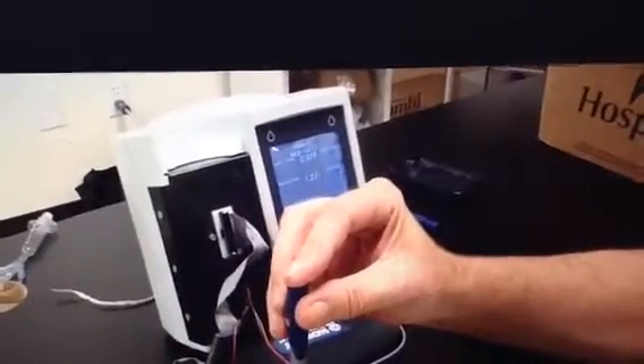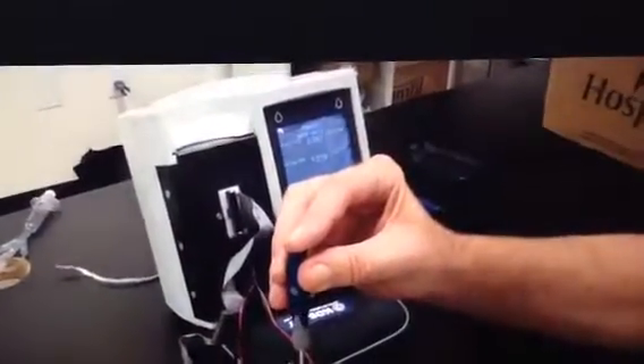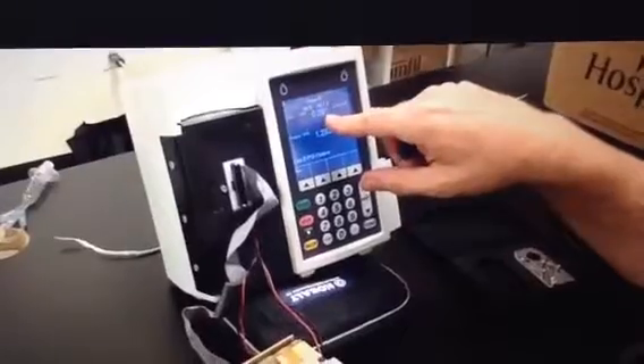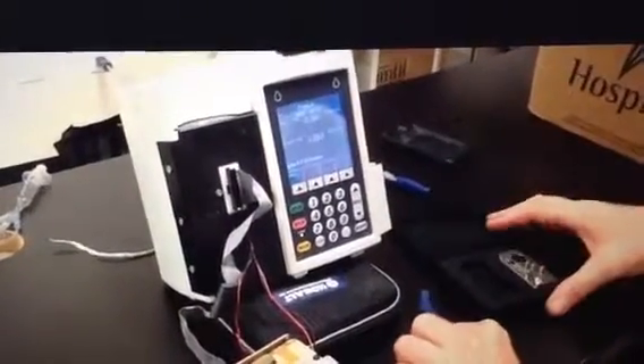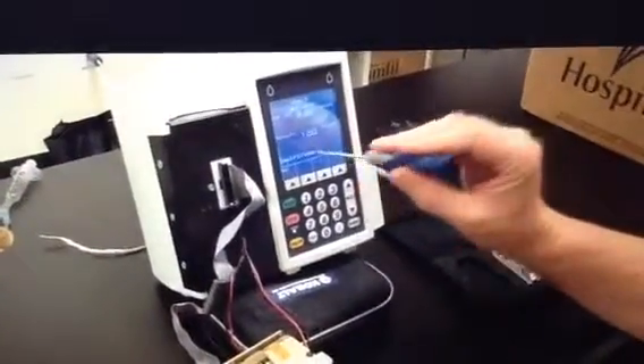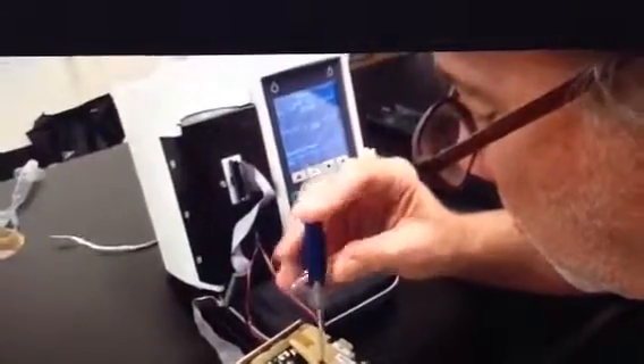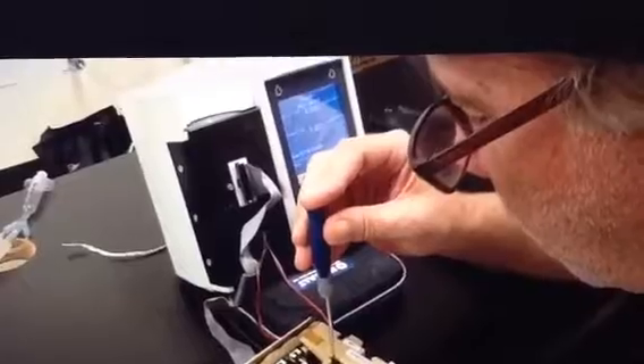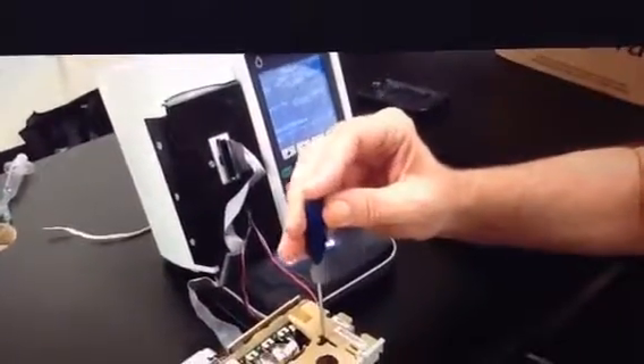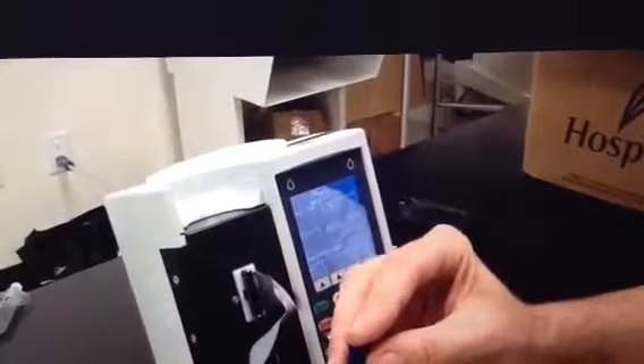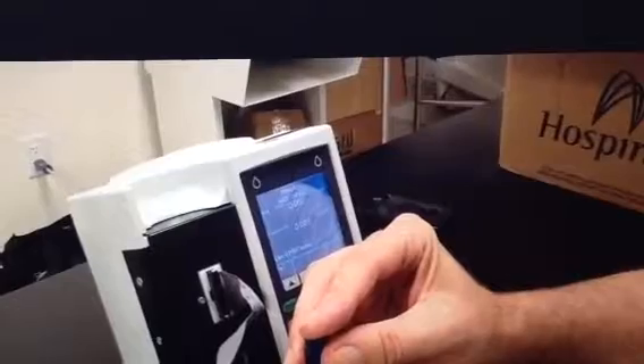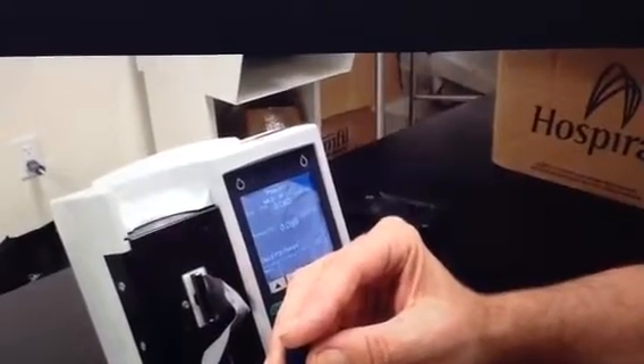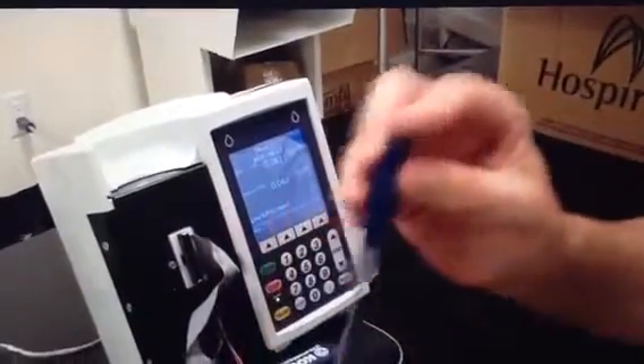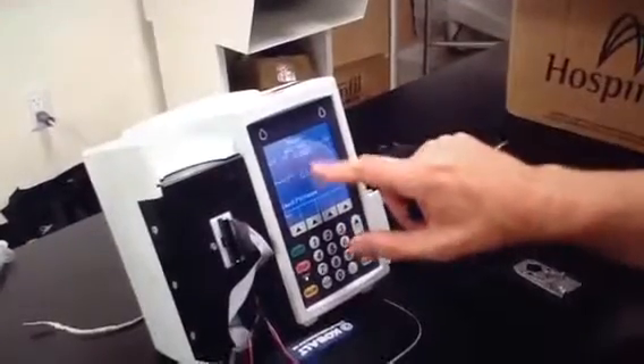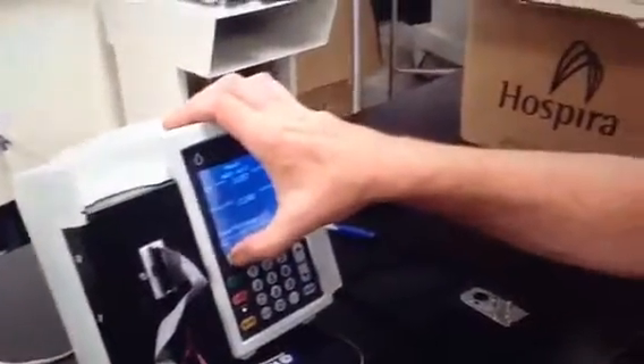And you see as we turn this counterclockwise, the voltage is going down. And there we have 0.06, which is between 0.02 and 0.08. Now we set our proximal 0 with the other potentiometer. If you go too far, you just have to go back the other direction. Now the pot is very sensitive, so you have to make very small adjustments. Okay, so we have both of these values in between where we need them to be, and we click Next.